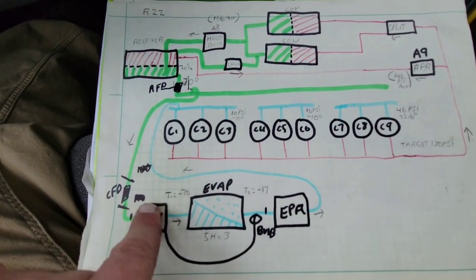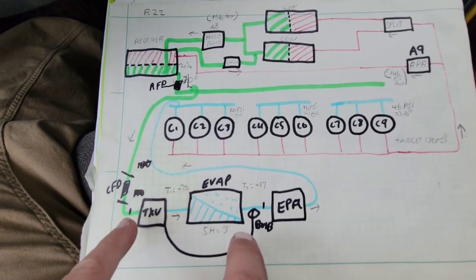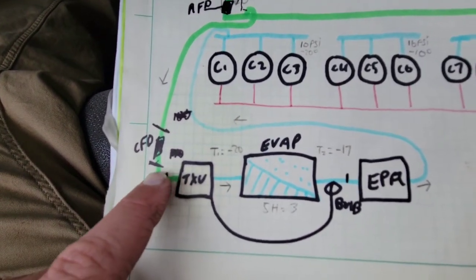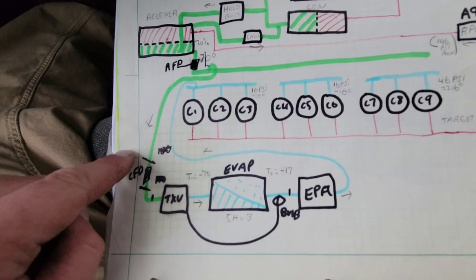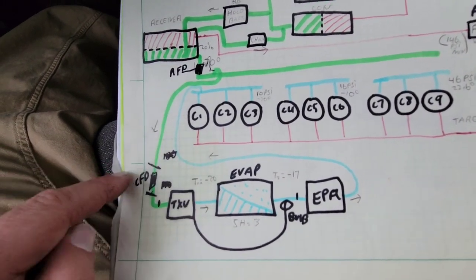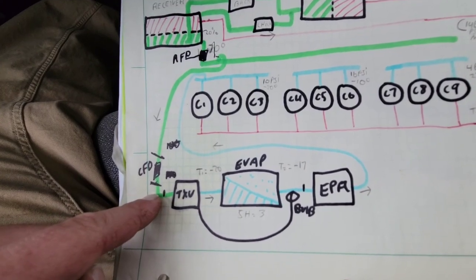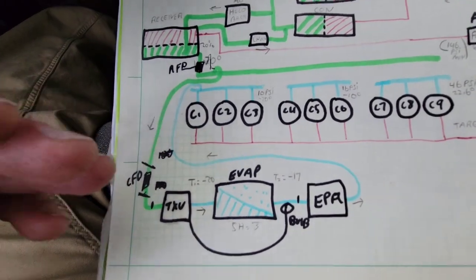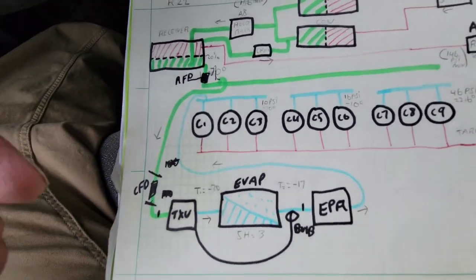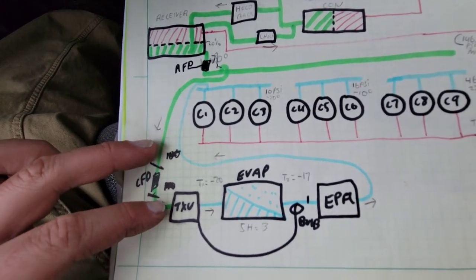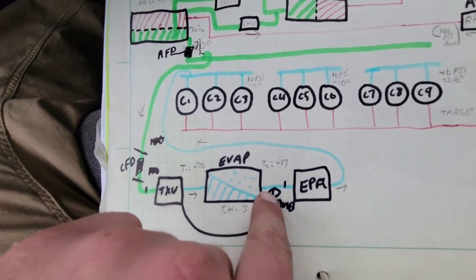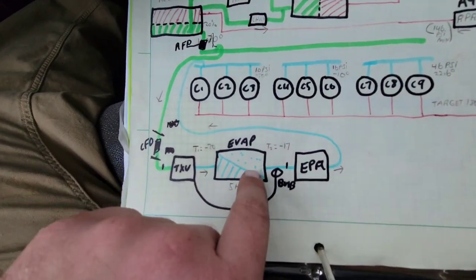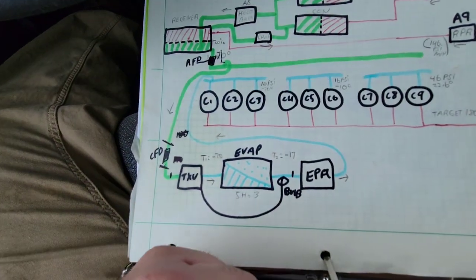I put it in my list like that because, for instance, if you check the pressures and there's a pressure tap after this filter dryer, and you find you've got 180 on one side and 120 on the other, that could be a very telltale sign, additional information to your temperature differential across the filter dryer, that the filter dryer could be bad. Also, you want to check your case pressure with respect to your specification.